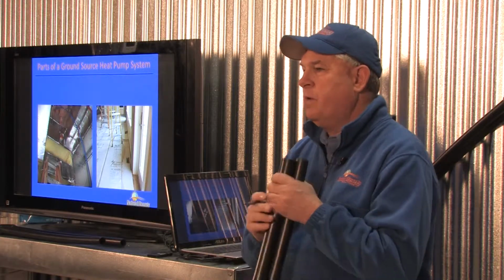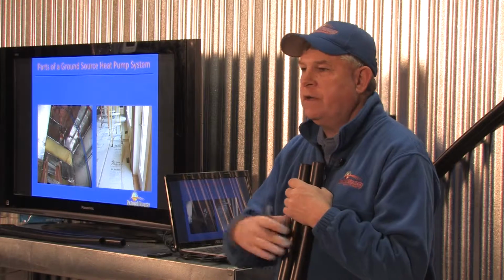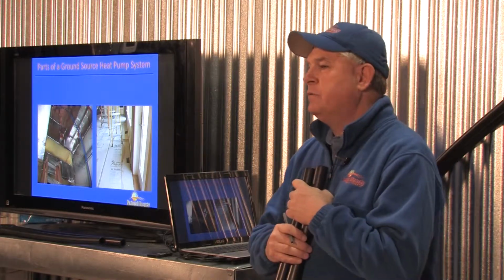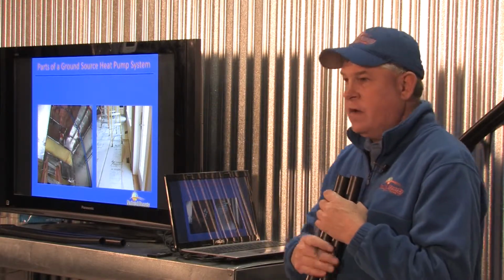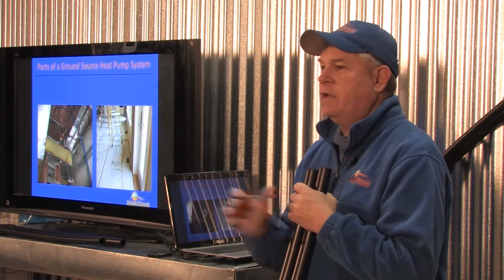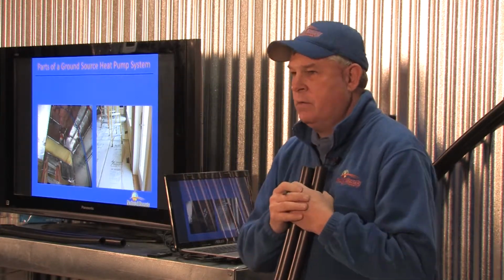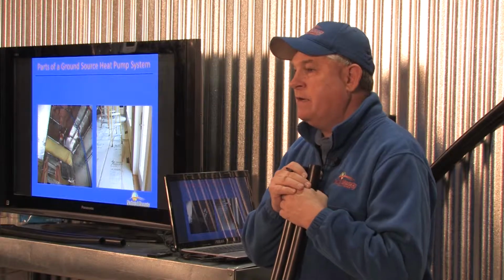We can also zone forced air. A geothermal system, a ground source heat pump, is a smart device. We can divide your house into multiple zones, 2, 3, 4, 5, 6 zones, that then talk to the unit and turn the unit up and down based on what the zone tells it needs. Only a ground source heat pump will do that. Your other forced air systems are on or off. So, it's a distribution system. It's a way to move the heat and the cool air through the house.